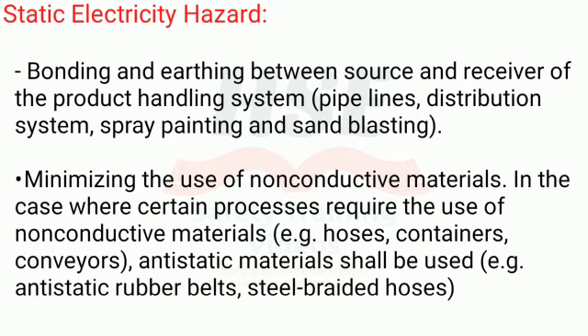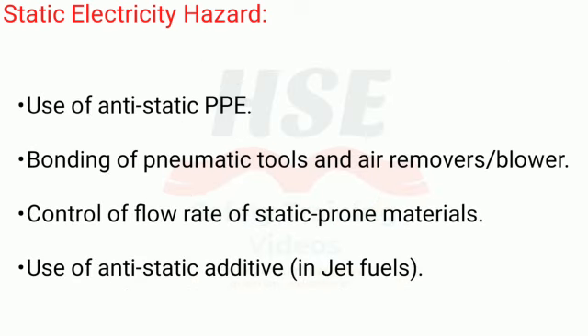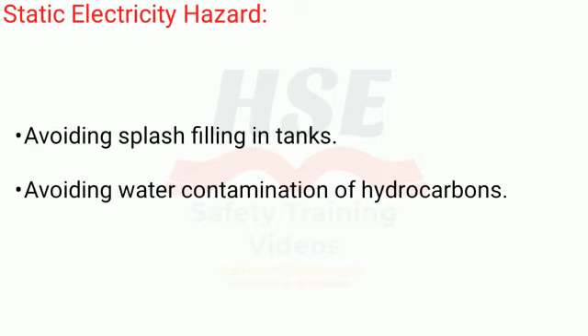In the case where certain processes require the use of non-conductive materials, for example hoses, containers, conveyors, anti-static materials shall be used, for example anti-static rubber belts, steel braided hoses. Use of anti-static PPE. Bonding of pneumatic tools and air movers, blowers. Control of flow rate of static-prone materials. Use of anti-static additive in jet fuels. Avoiding splash filling in tanks. Avoiding water contamination of hydrocarbons.